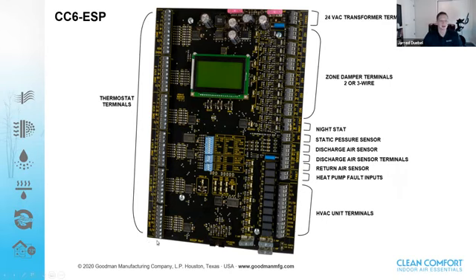It's got a lot more going on than our 3 zones. So the zone damper for each zone is actually on the other side of the panel. So you have zone 1 and then zone 1 damper, zone 2 damper, and so on and so forth. You're going to power it up and wire the thermostats up just like our 2 and 3 zone panels. Again, indicator LEDs. So all these little white LEDs here, those are all the zone damper LEDs.